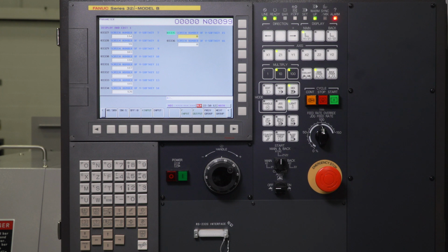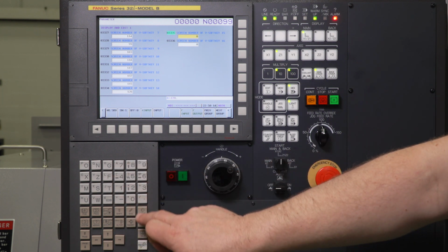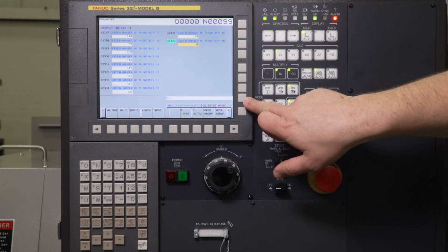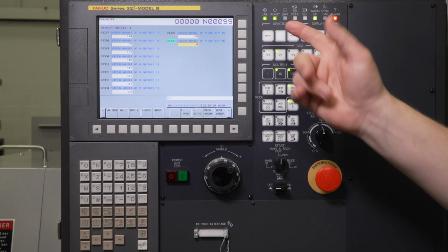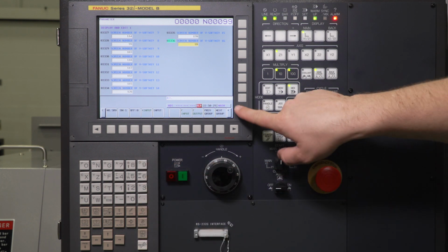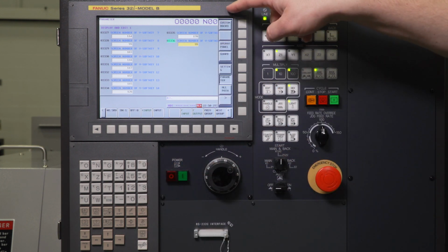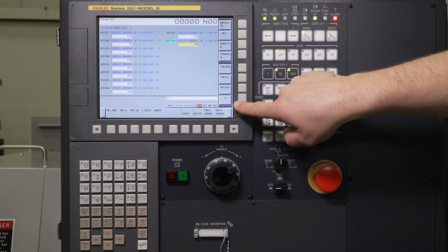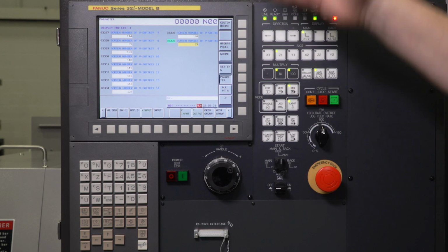3335 will be alarms. So if I do 170 input, and then again, this is number 16, which would be the bottom one. This has to be a 99 in order to get you back to screen number 1. So 99 input. So now when I press here, I'm on page 2. I press my arrow. It's going to bring me back to page 1. So I've now customized all of my shortcut keys.